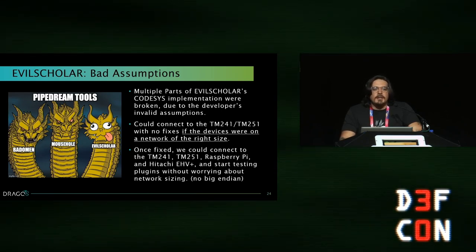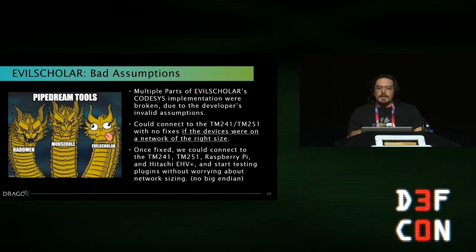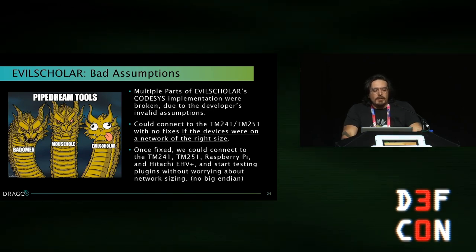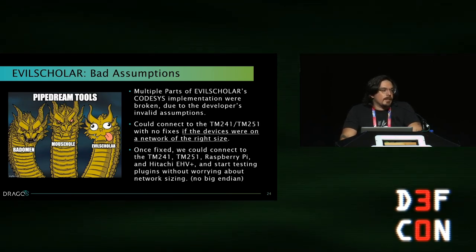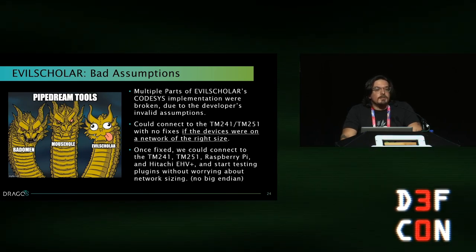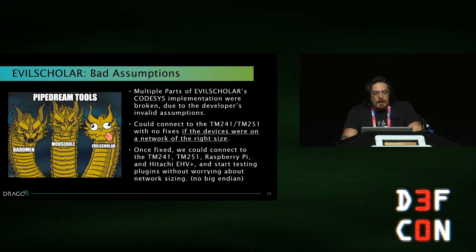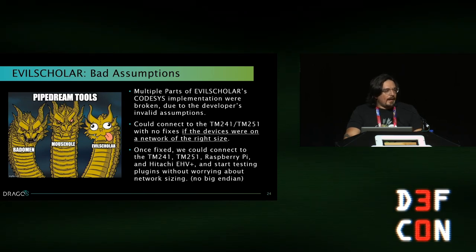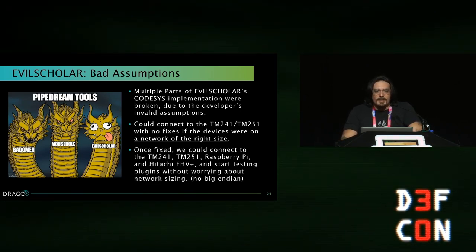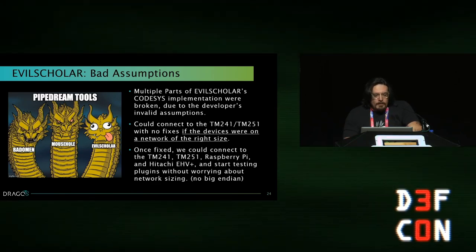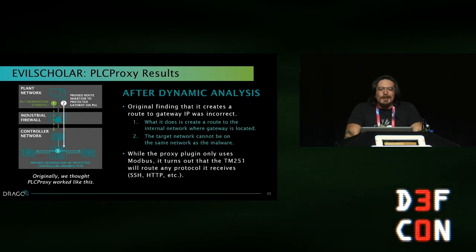We had a lab where we could connect to devices just fine and another where we couldn't connect at all. This took us the longest to sort out. We thought it was a firmware issue, but it turned out Evil Scholar is the problematic one in the group — the developer made poor assumptions about CODESYS, including assumptions about network size and address sizing, which is variable length in CODESYS. The default version of Evil Scholar could connect to the TM241 and TM251 with no fixes if devices were on a network of the right size.